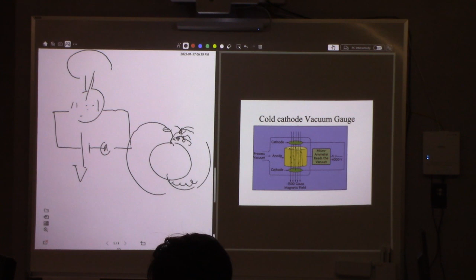So, this ion gauge that we talked about is basically the hot cathode gauge, right? That's the difference. This one is basically to emit heat and emit the electrons, right? Then you just measure the current. Depending on the current, whether these ions can reach here, you will measure this current. Basically, this is a hot cathode. The ion gauge is basically a hot cathode gauge.